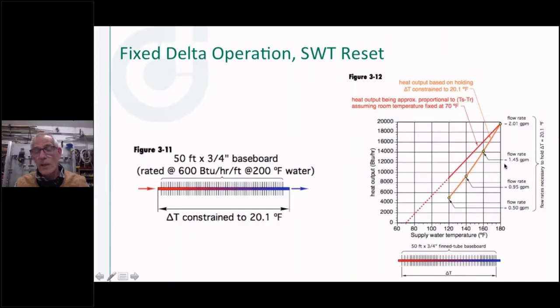The other thing is when you try and regulate a heat output by varying the flow rate, it's a very non-linear thing. As you can see how these curves, or these two lines, these slopes, let's call them, they start to split apart, where in the previous drawing, they paralleled each other. And that's why the outdoor reset can almost perfectly match the heat loss of a building, because the temperature is pretty closely related. The amount of temperature you have to increase as the load on the building increases, and vice versa, is a fairly consistent parallel curve. So it makes it pretty predictable and pretty easy to dial in a boiler with an outdoor reset.